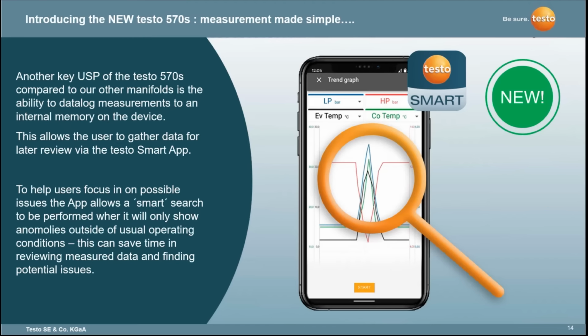And then the idea is you set the device running, you can maybe go off and do some other work, which leaves you much more flexible to then come back, stop the data logging sequence, harvest the data, and then using the app, you can use a smart search where, rather than have to plow through hours and hours of data, it only shows you what it considers are anomalies outside of usual operating conditions. So the idea is you can then hone in on particular issues, saving time on reviewing lots and lots of data. But the data logging is set up with the smart app, so the memory in the device is actually doing the logging, but then the device will transfer that logged data by Bluetooth across to the smart app on your phone for you then to review it.